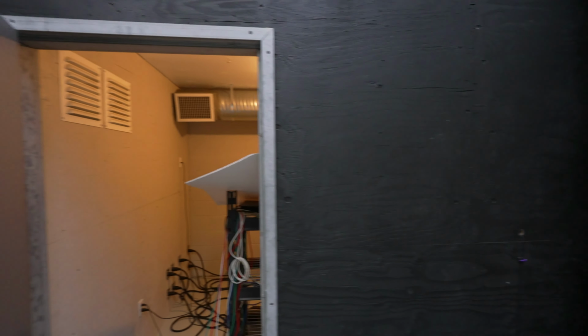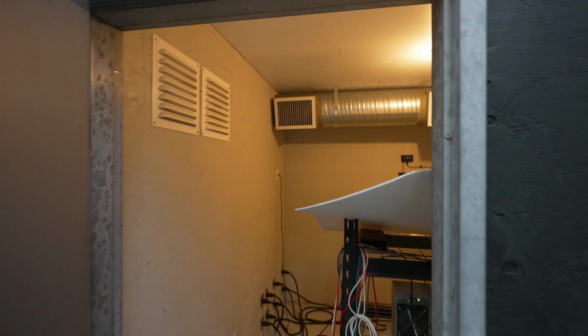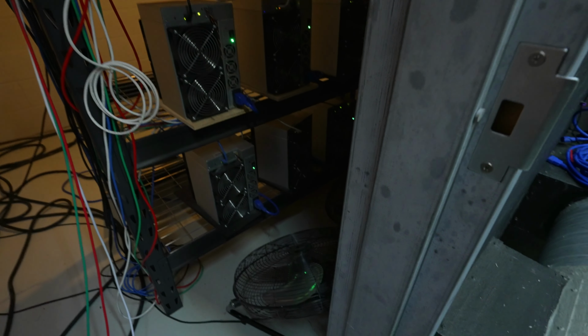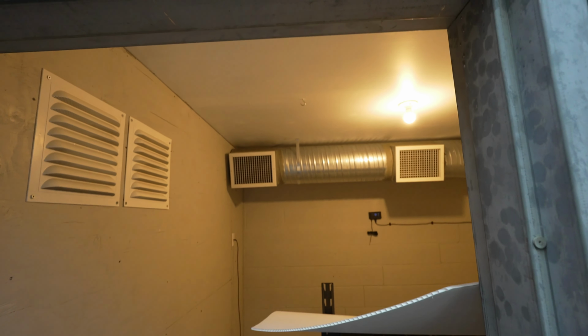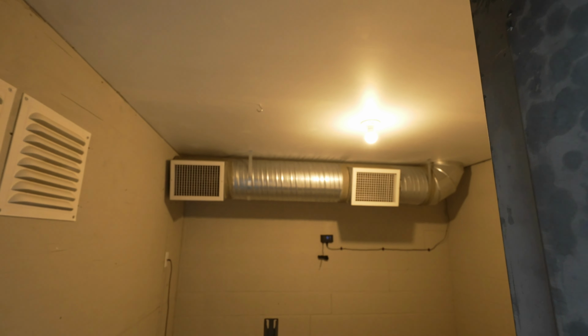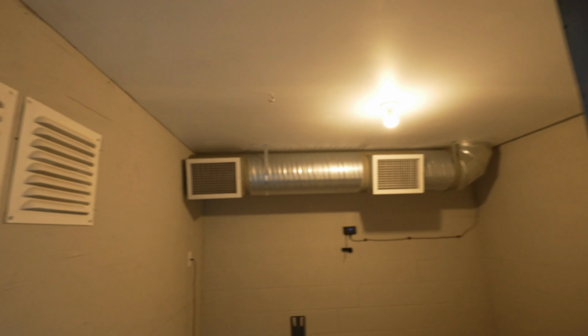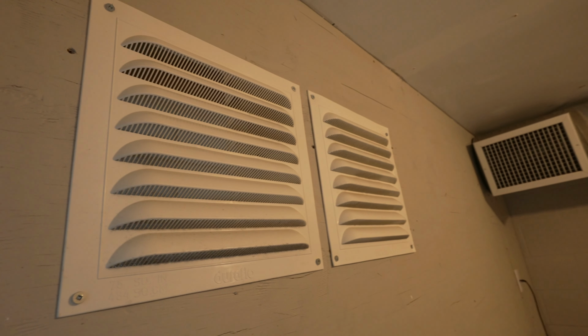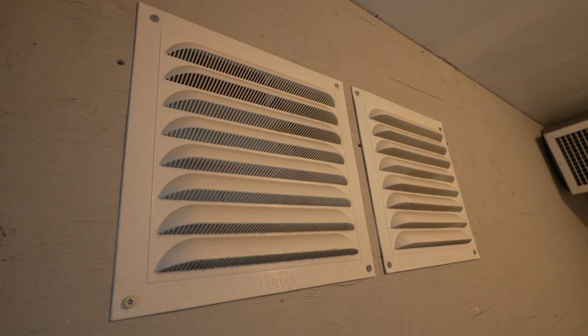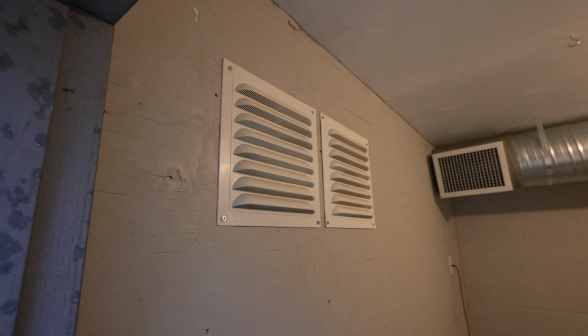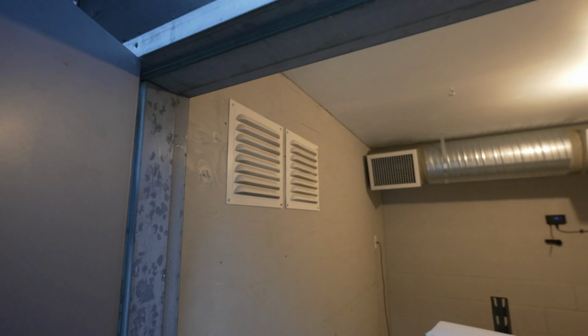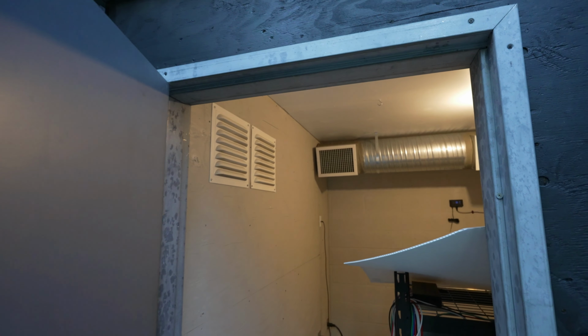Honestly, that just didn't work for us, because our cold aisle was fine temperature-wise, but the exhaust wasn't exhausting the room quick enough. So one of the first things we did was cut vents into the side of the building, and it actually helped big time, dropping the temperature of the hot side by about 2 degrees.